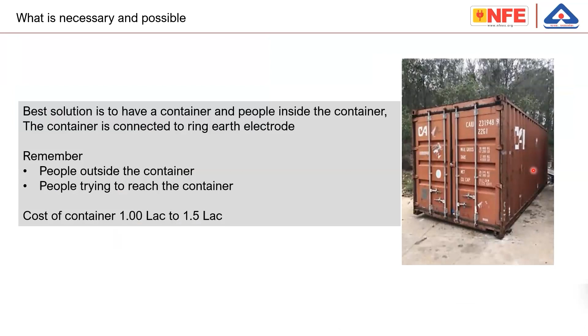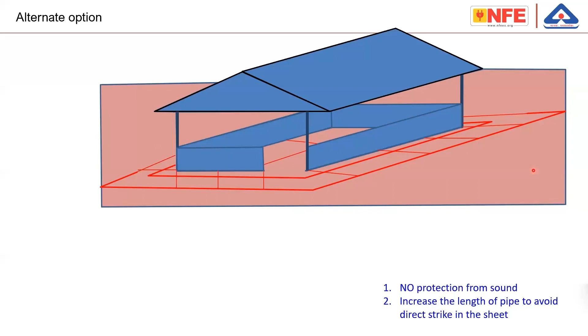One method which can be thought of is, instead of a metallic container, you can make a metal shed with metal supports, and this red color is nothing but several ring conductors outside the building and inside the building, in order to make the earth potential uniform. So this may be a solution. It is not scientifically proven; if required, through software we can analyze, simulate, and test whether this will work if there is a demand. But this can be a practical solution. A metal shed with metal supports means the roof is properly grounded. Then on the earth, all the metal poles are interconnected to a kind of grid all around the area, inside and outside the building, so that potential equalization is also made.